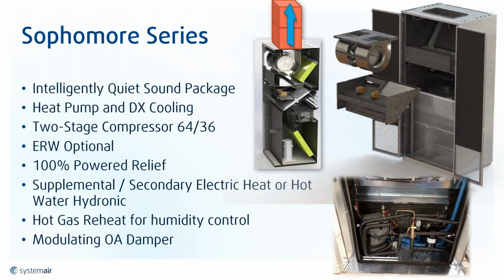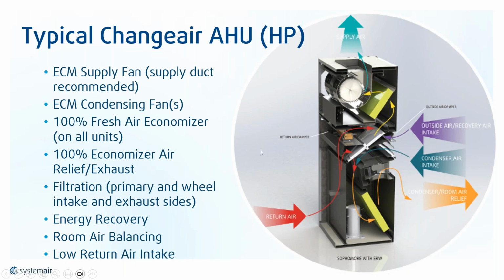So again, what does the sophomore series give you? It gives you the IQ sound package, the heat pump or DX cooling, 2-stage compressor, energy recovery wheel, optional, everything I just mentioned, the hot gas reheat for humidity control. So it's really a very tightly packaged system. Just showing you here a typical airflow, right? This is returning from the classroom, and gets mixed through the wheel or exhausted, and then outside air intake. So you got a lot crammed into here, especially if you take, as I mentioned before, the hot gas reheat, the energy recovery wheel, the 5-ton compressor, etc., with extra backup heat if needed.